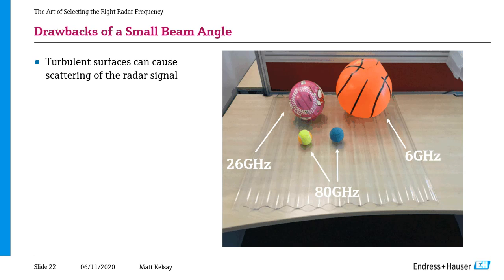If you move over to the pink ball now, that's a little bit smaller, more representative of a mid-range frequency unit. So again, you drop that ball from above, probably 9 out of 10 times, it's going to come straight back up and you're going to get a good signal return. However, now if you look at the tennis balls, that's representative of an 80 gigahertz, so really small beam angle. And if you drop that tennis ball from above, maybe only half the time it's going to come straight back up. So sometimes you get a good signal return, sometimes you don't.